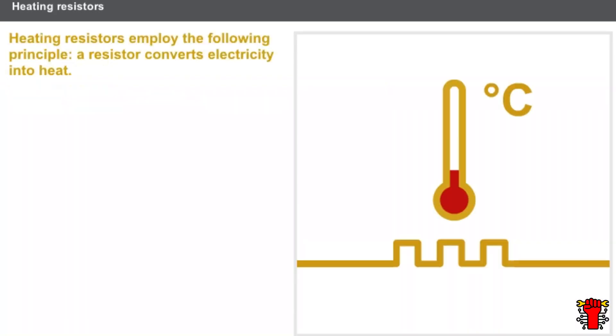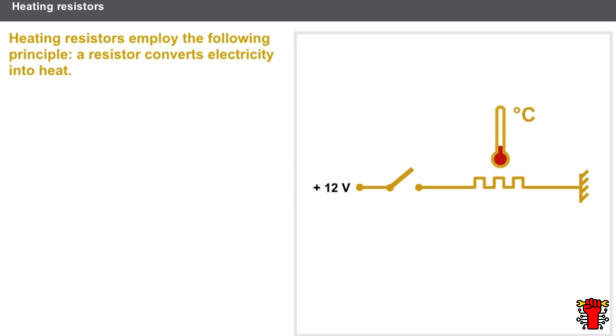Actuators employ various principles according to their function. Heating resistors are a first type of actuator. A resistor converts electricity into heat. Heating resistors are mainly positive temperature coefficient thermistors. The power supply for the heating resistors is time delayed and generally controlled by a relay.